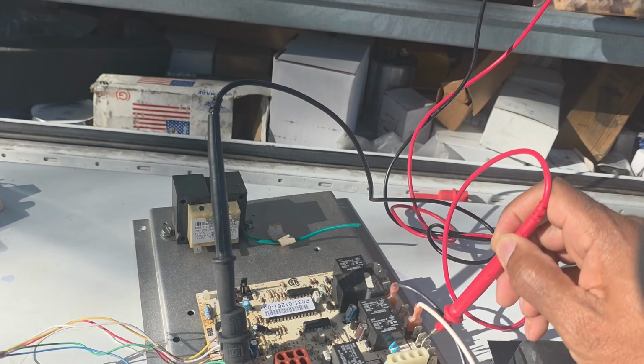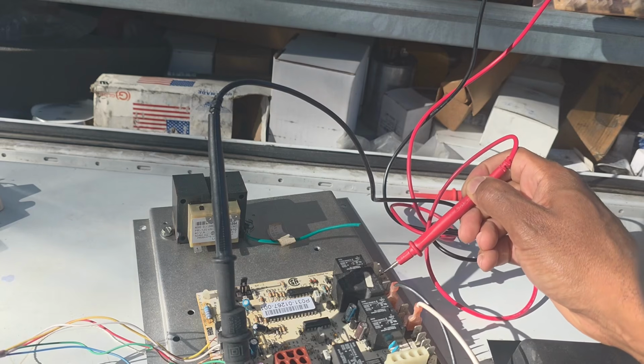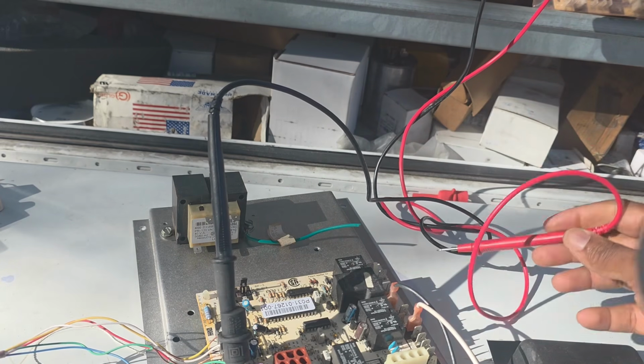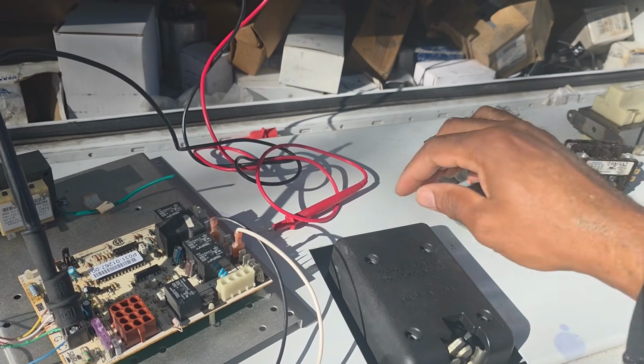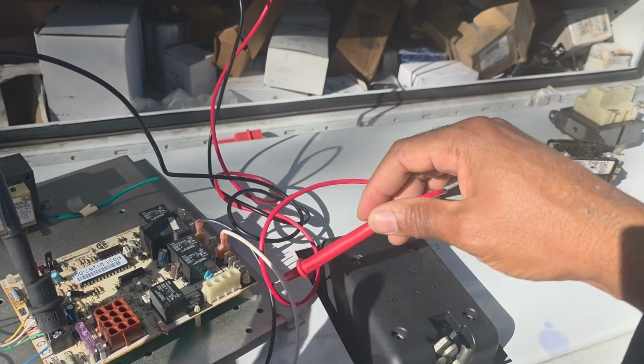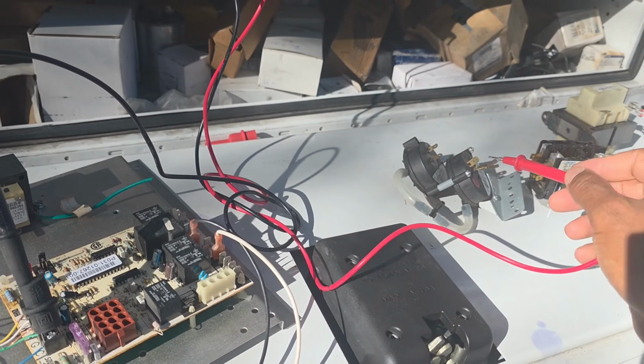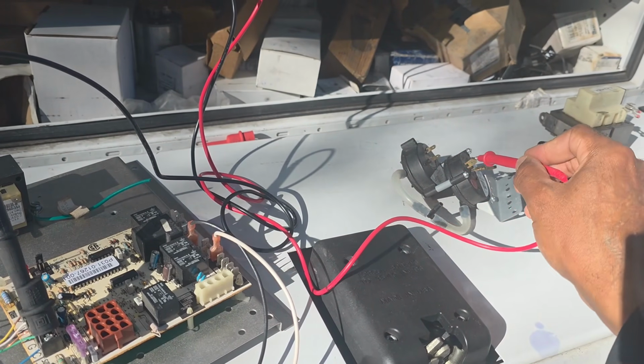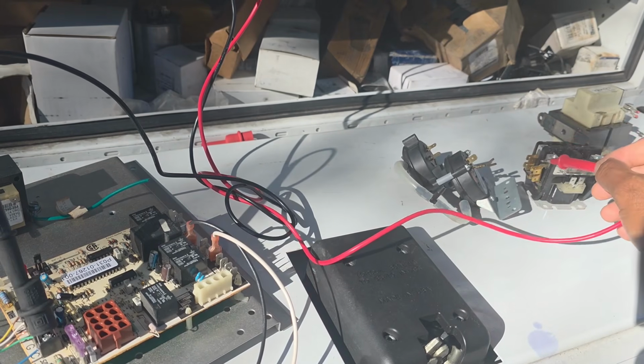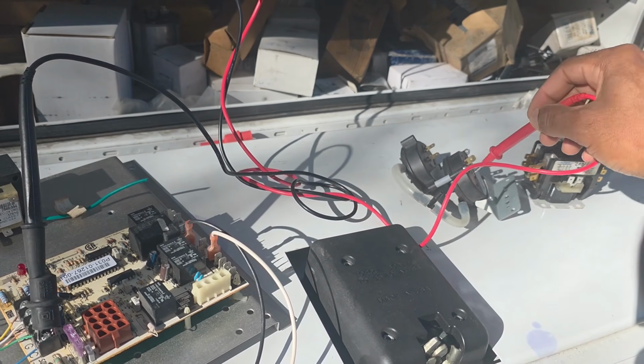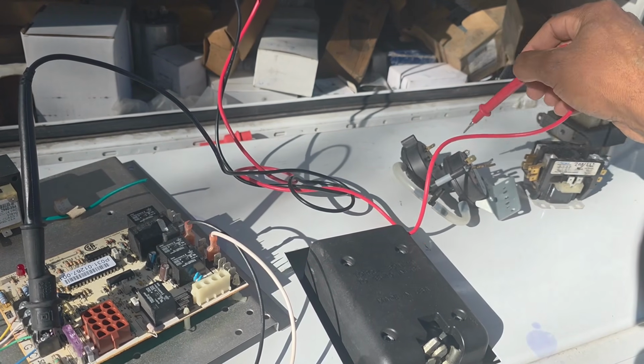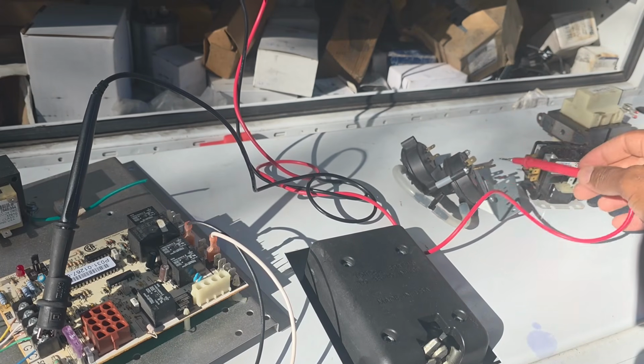So we're just going to go to terminal, checking for voltage. All right. Like I say, this is almost showing like the unit is not on. This method would do no good if you don't have power to the unit. It won't do nothing. Your meter won't change. It'll just be zero because you don't have power. But let's go to the unit.